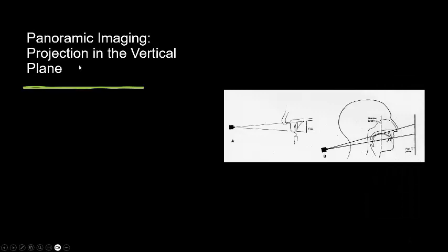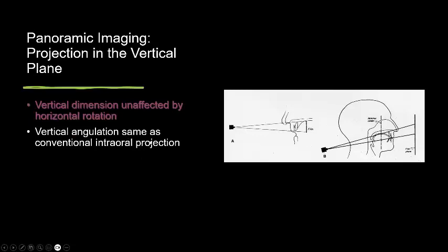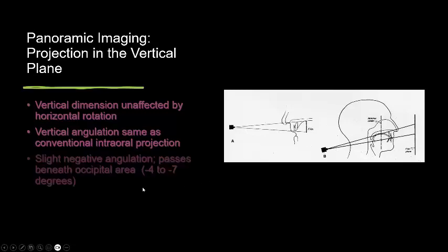Regarding panoramic imaging projection in the vertical plane: vertical dimensions are unaffected by the horizontal rotation. Vertical angulation is the same as in conventional intraoral projection, with slight negative angulation passing beneath the occipital area — approximately minus 4 to minus 7 degrees.